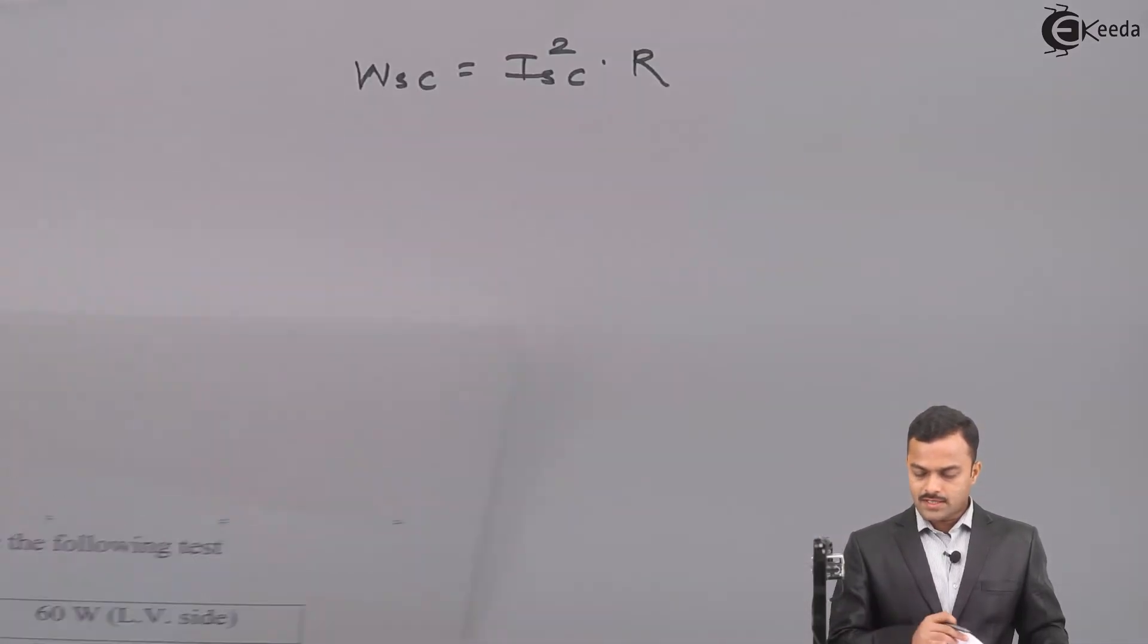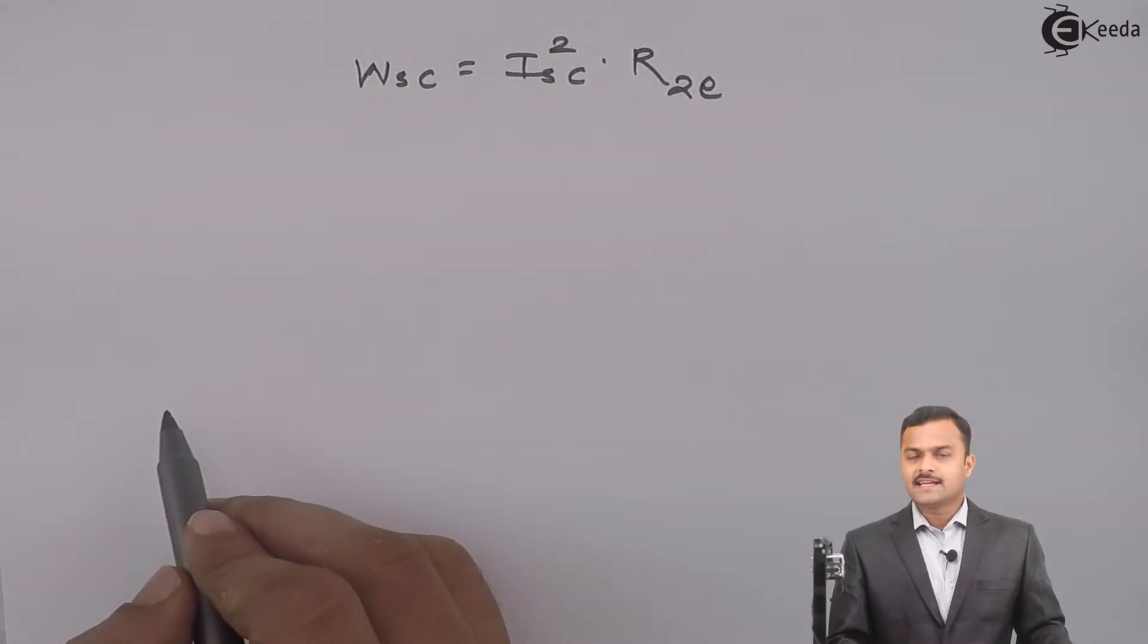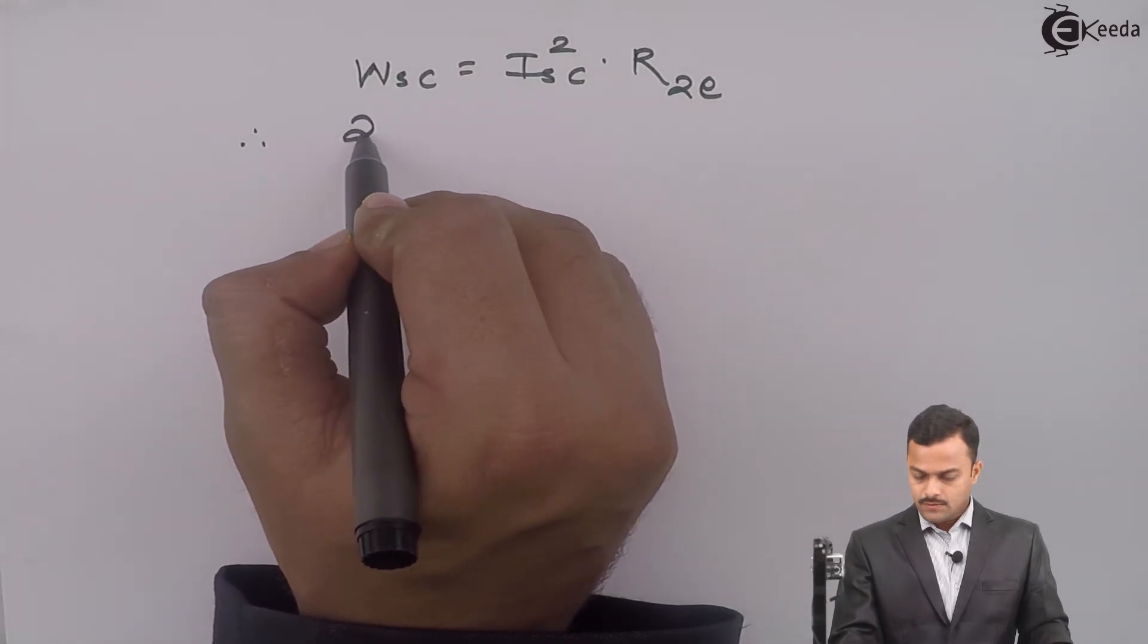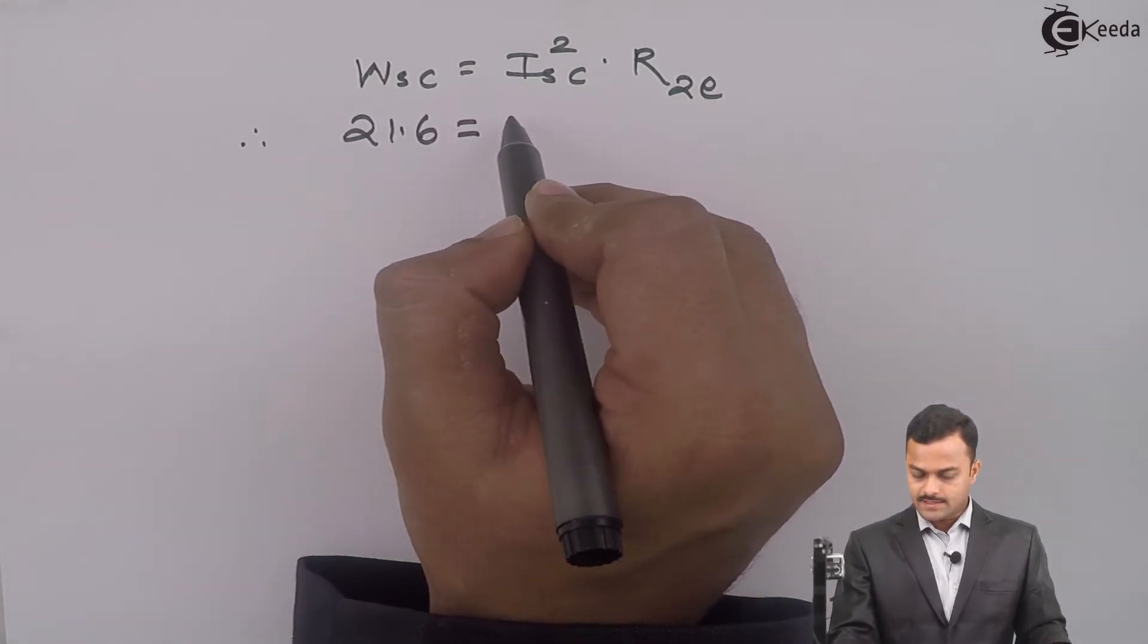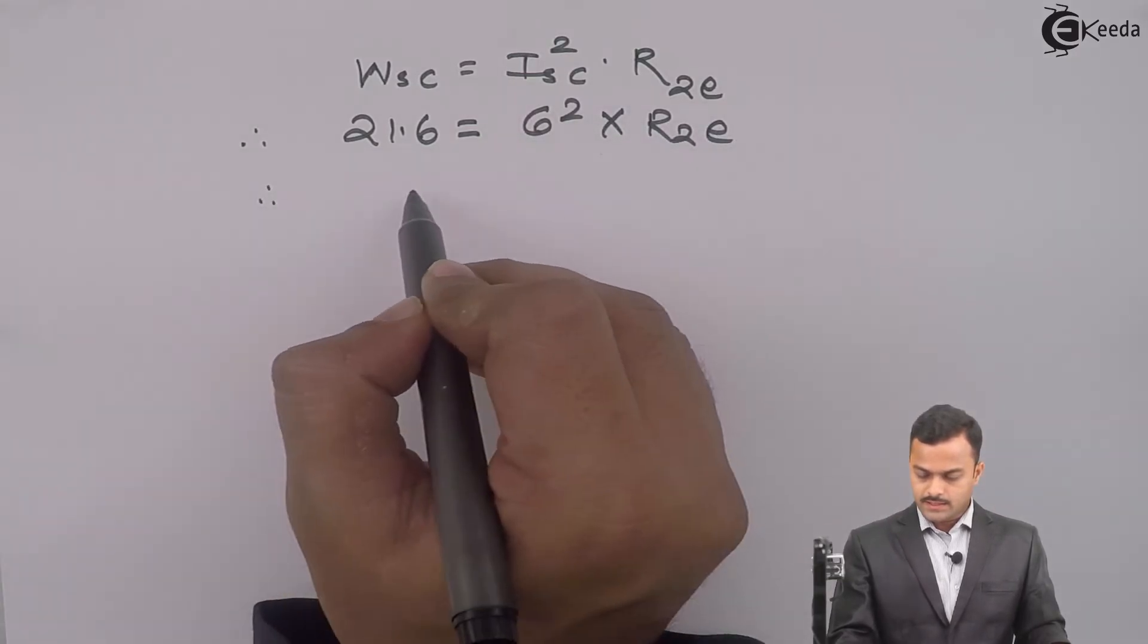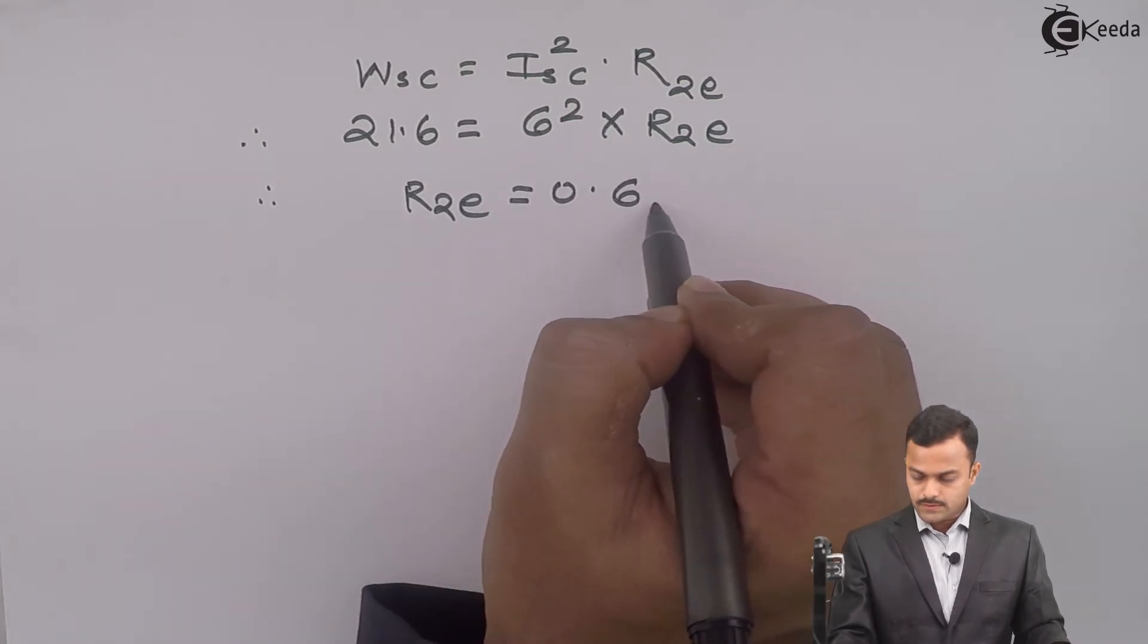Short circuit test is performed on high voltage side. Here, high voltage is secondary. So obviously, I have to take secondary referred resistance R2E. WSC is 21.6, ISC is 6. If you solve, you will get R2E equal to 0.6 ohm.